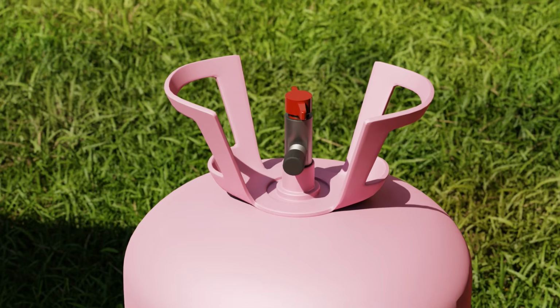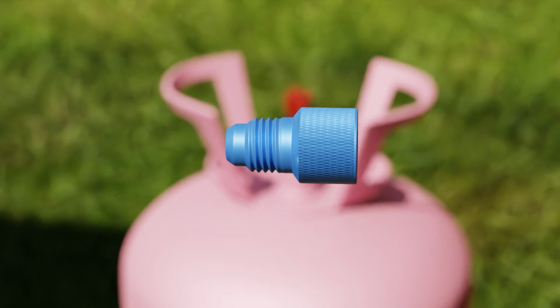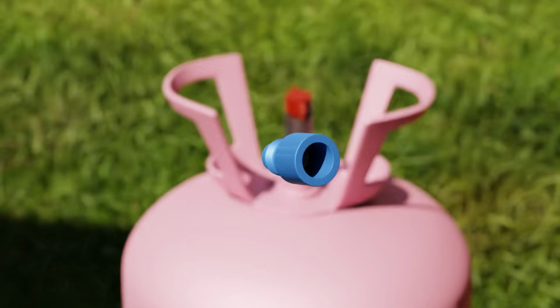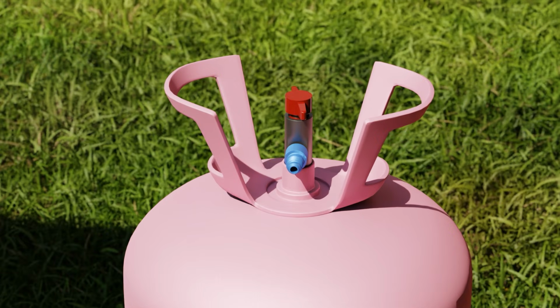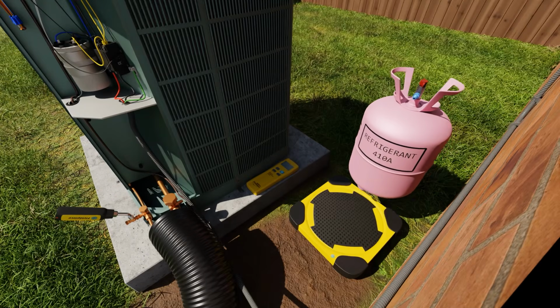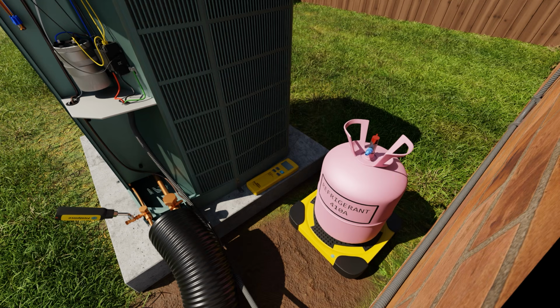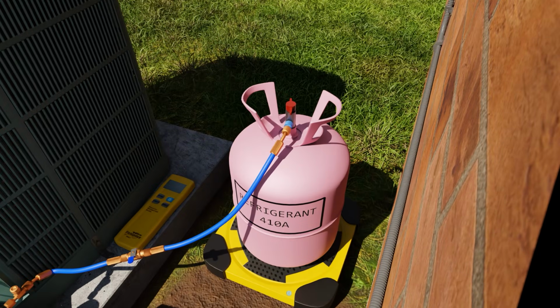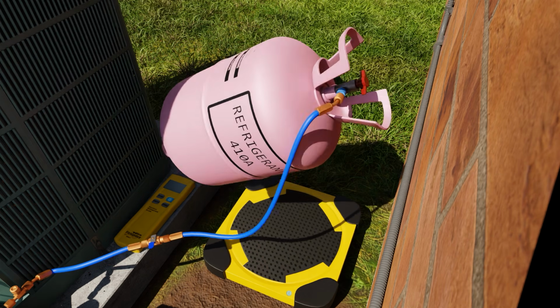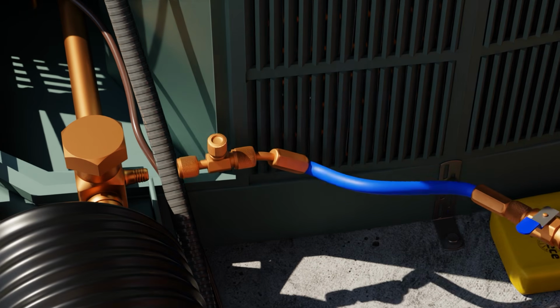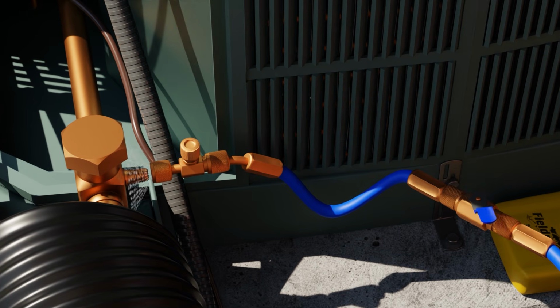You'll also want to use a charging orifice on the tank because you'll need to charge in the liquid state. This ensures that you won't get liquid into the system as you're charging while it's running. It's worth noting that if you measured your line sets beforehand and you know you need to weigh in a certain amount of charge, you could do that before you even release the charge from the system into the line set. You can charge it into the line set when the system is still under vacuum. This will save just a little bit of time.